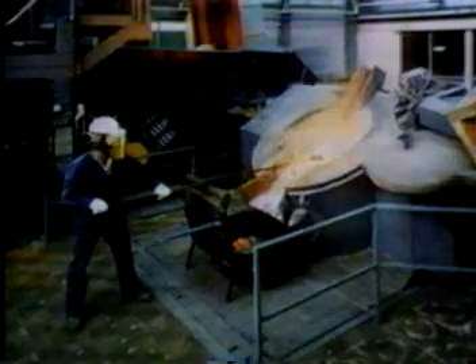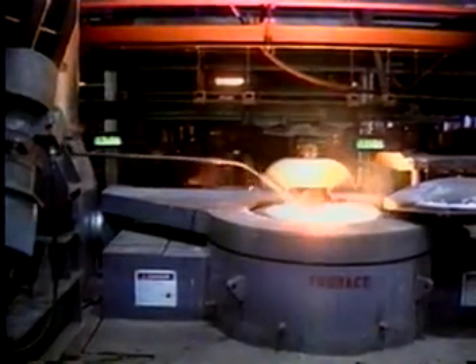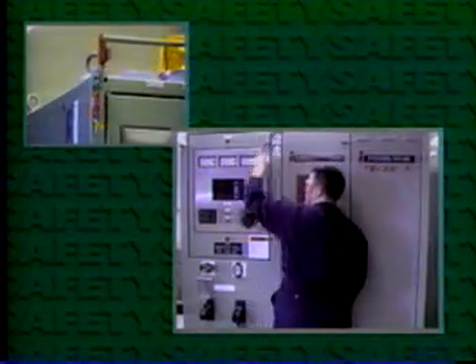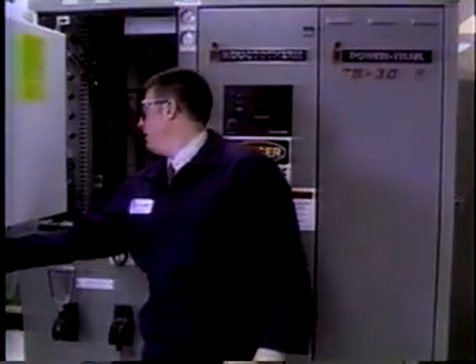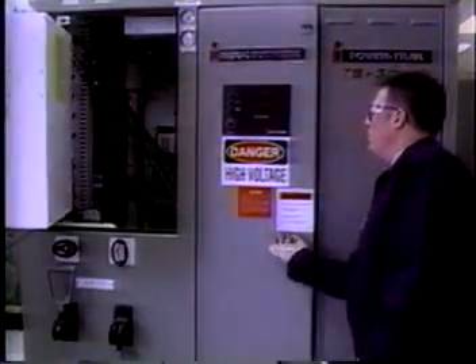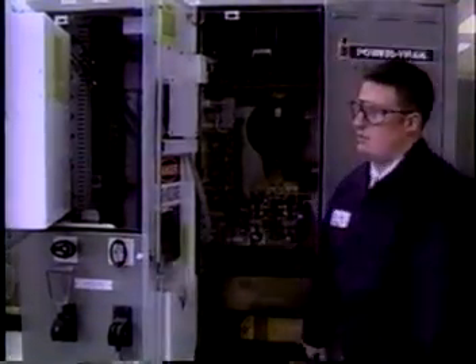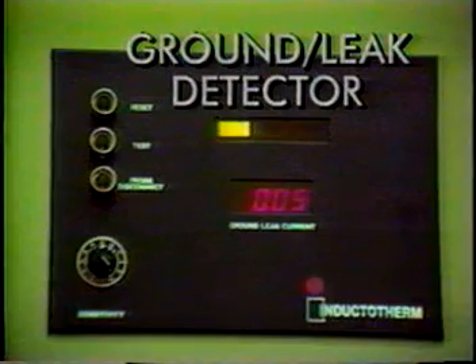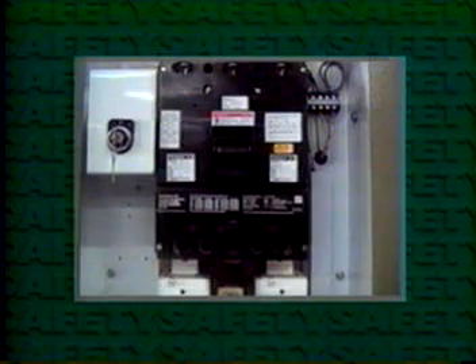This is to prevent shock or electrocution if the metal bath were to come into conductive contact with the induction coil. In addition to the safety interlocks designed to turn off power automatically when power cabinet service access doors are opened, modern induction melting equipment normally includes a variety of other key safety systems. Ground leak detection systems turn off power if metal in the furnace comes close to or touches the induction coil. This serves both to help prevent a runout and to reduce the chance of shock or electrocution from power conducted through the bath.